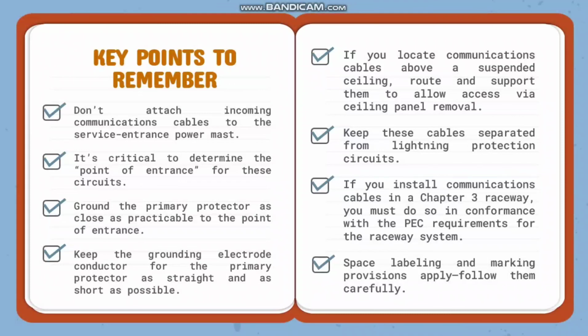Fifth, if you locate communications cables above a suspended ceiling, route and support them to allow access via ceiling panel removal. 6. Keep these cables separated from lightning protection circuits. 7. If you install communications cables in a Chapter 3 raceway, you must do so in conformance with the PEC requirements for the raceway system. And last, space labeling and marking provisions apply, follow them carefully.